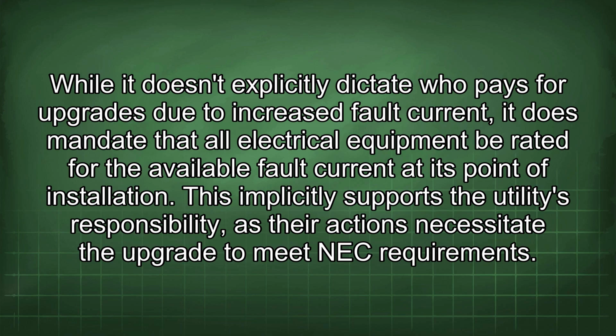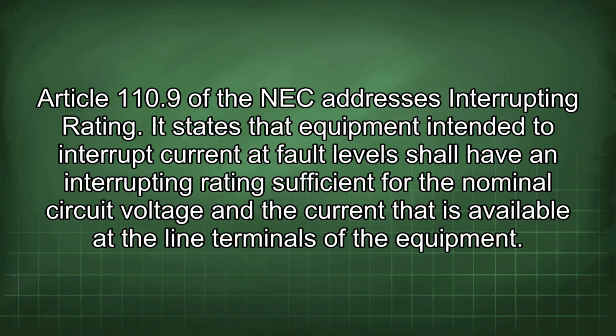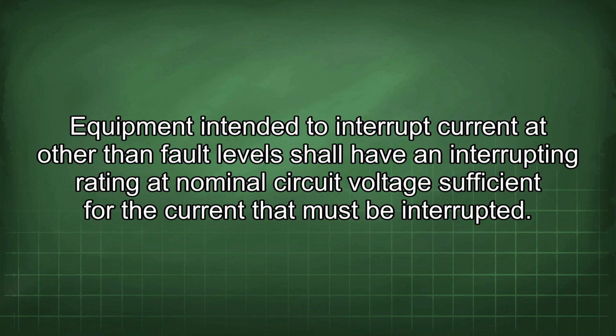This implicitly supports the utility's responsibility, as their actions necessitate the upgrade to meet NEC requirements. Article 110.9 of the NEC addresses interrupting rating. It states that equipment intended to interrupt current at fault levels shall have an interrupting rating sufficient for the nominal circuit voltage and the current that is available at the line terminals of the equipment. Equipment intended to interrupt current at other than fault levels shall have an interrupting rating at nominal circuit voltage sufficient for the current that must be interrupted.